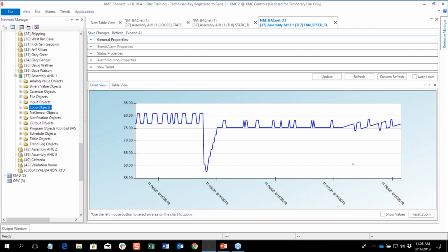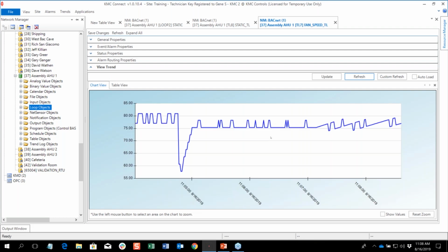Maybe I can give you an example of some reasons why you would end up with a steady state error. If you think about a room and you're doing room temperature, the heat gain in the room maybe equals the heat loss to the outside. So there becomes this balancing point where the amount of heat you're adding to the room, you're also losing outside, and it's perfectly balanced.